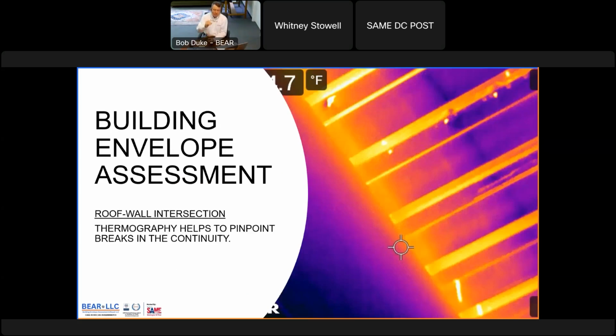So being here in Charleston, and it's almost July 1st, we are now in the season of what they call the 90 and 90s, right? 90 degree temperatures, 90% humidity. When you have hot, moist air with an influx like that, that is going to hit your cold ductwork. It's going to condensate, drip, create mold. So it's really important that we try to identify precisely where all this hot, moist air is coming in. Next slide, please, Whitney.